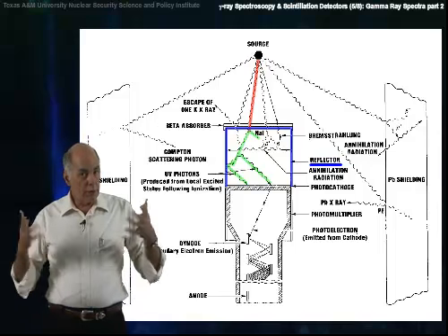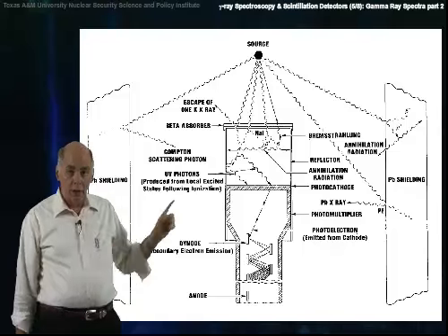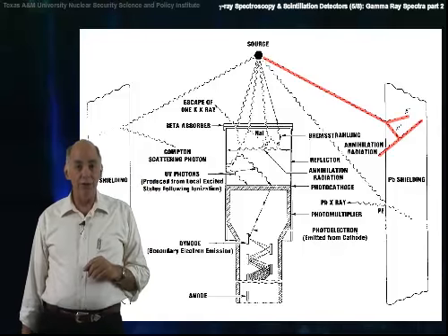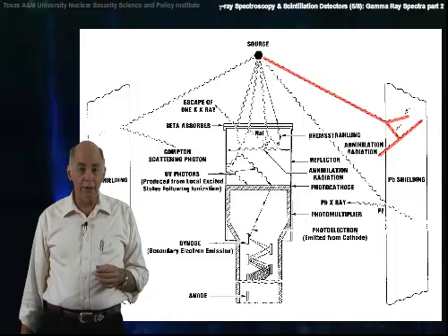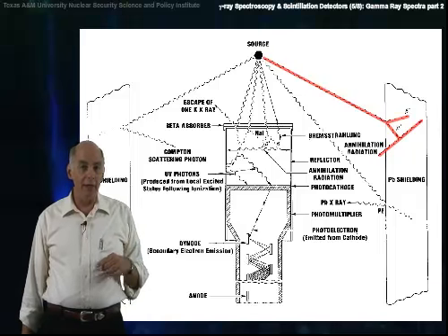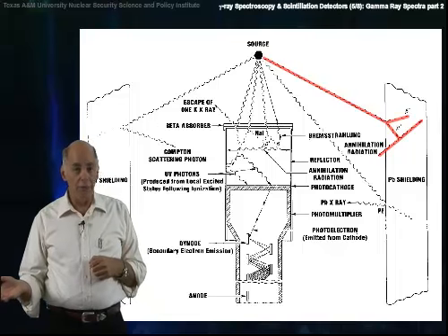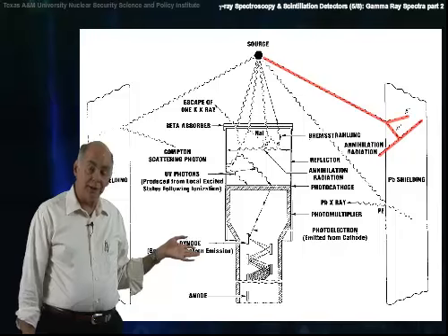Now, let's focus on the surrounding materials. This gamma from the source strikes lead shielding surrounding the detector, creating a positron that annihilates, creating a 511 keV photon that can now enter the detector.